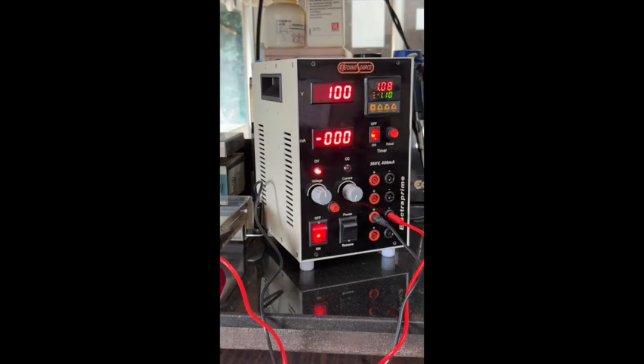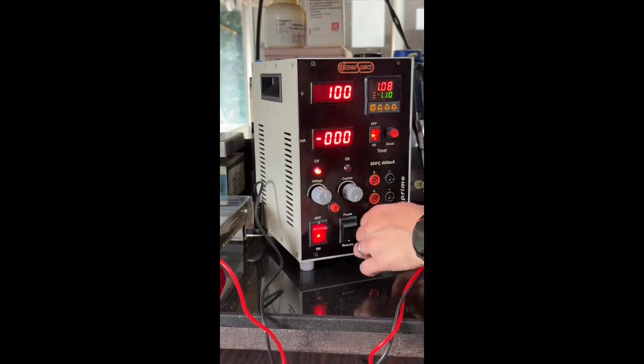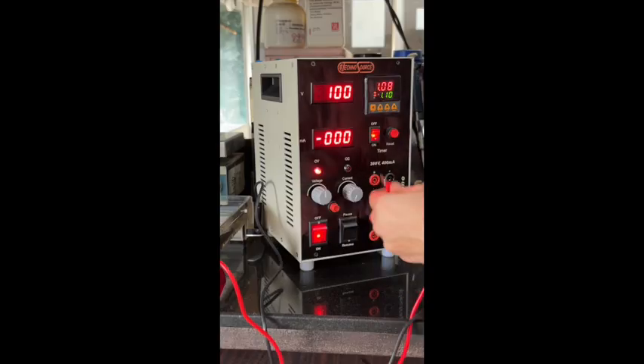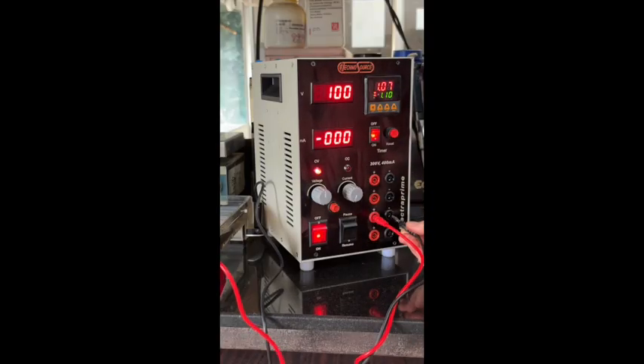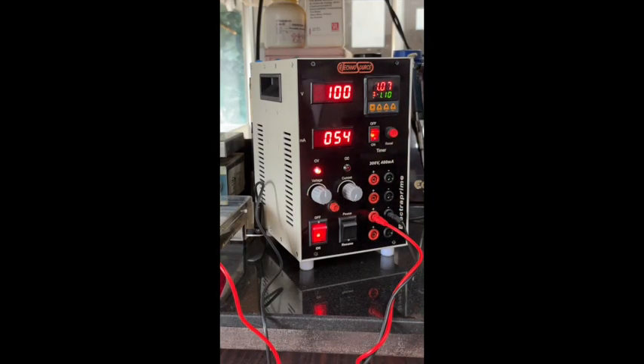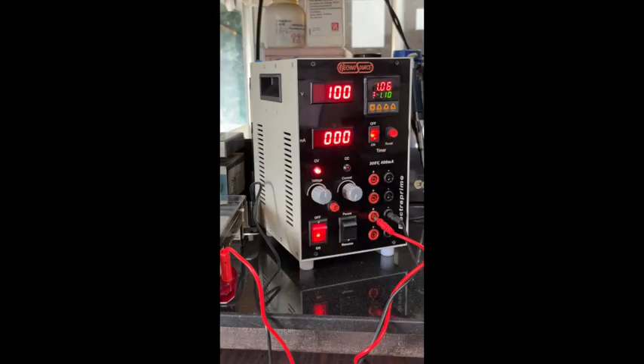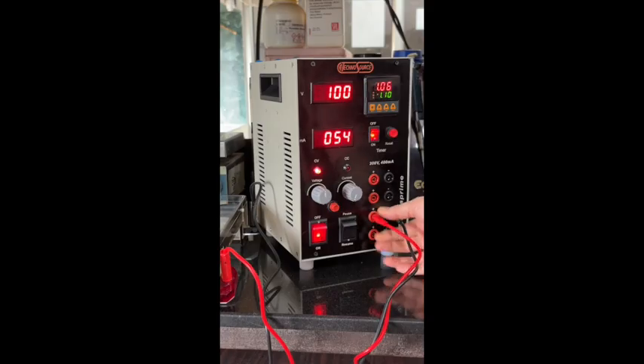Cause number 2. Cathode and anode are not connected to the right output terminals. Remove and reinsert the cords to the power supply and to the apparatus in the correct orientation, that is red to red and black to black. Cause number 3. Electrical connecting cords are not properly inserted. Remove and reinsert the electrical connecting cords properly. Make sure there's a tight fit between the male connectors and female connectors.